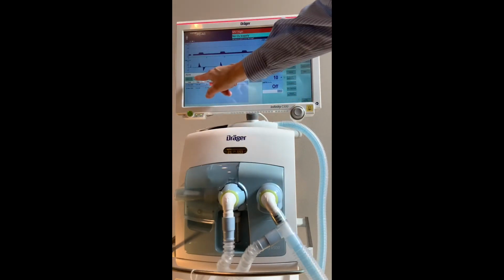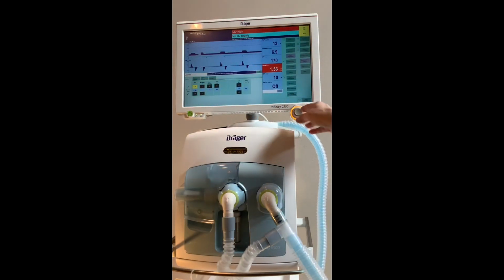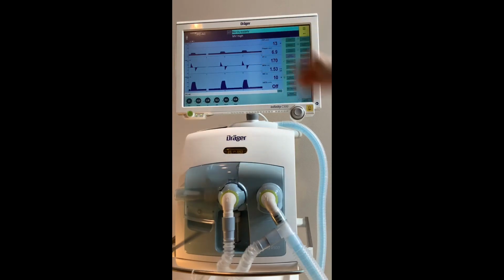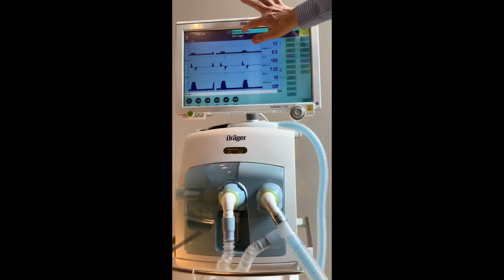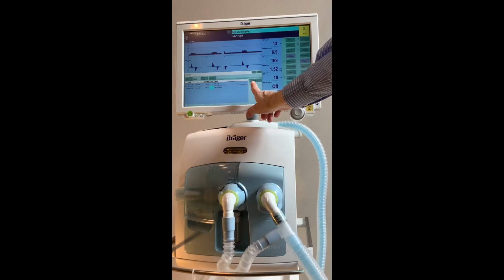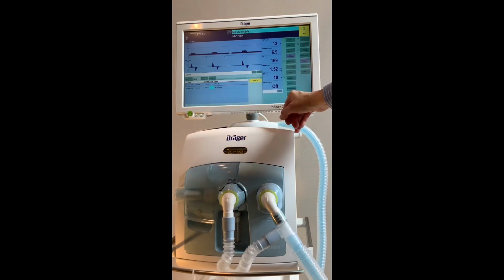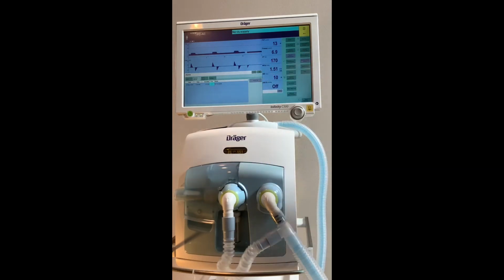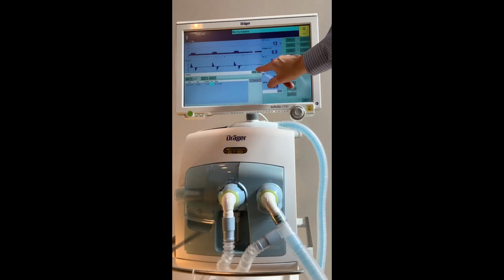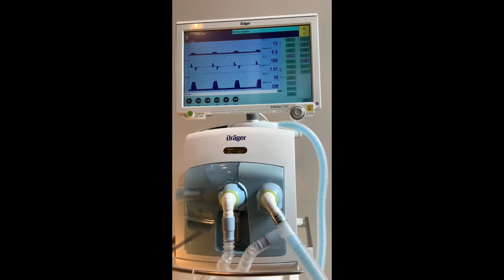Once the alarm is resolved, the message stays on the screen. If you touch the screen, you will get a button that says Reset All, and that will clear away all messages that are either old messages or alarms that have resolved. To clear the screen, you touch the X, and that will take you back to your main monitoring page.